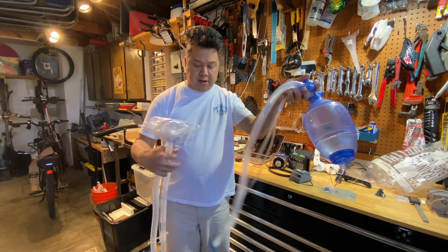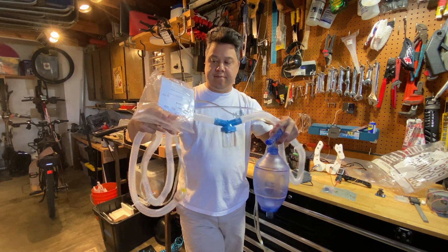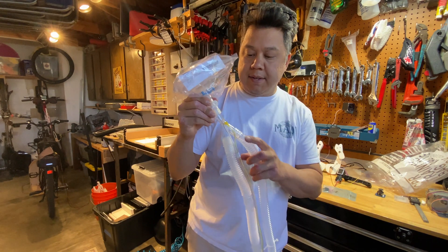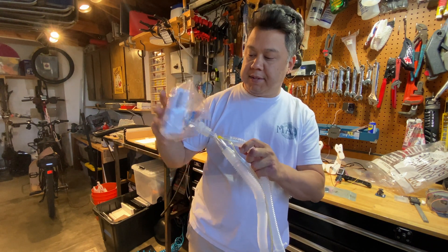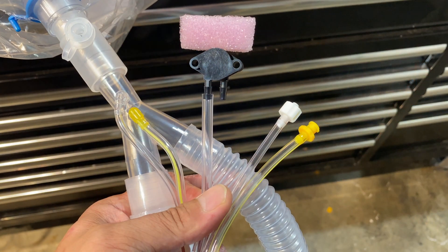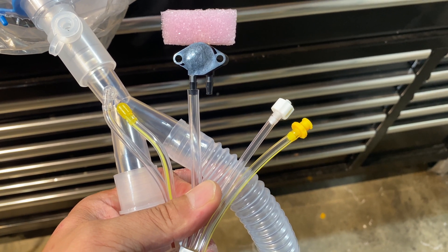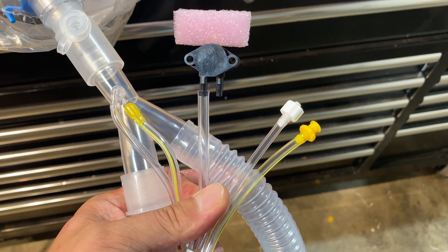Air flows through this intake hose, through a water separator cup, and into this Y which supplies air to the mask. The splitter has some tap lines and I'm using one of those tap lines to hook up my pressure transducer. This will measure pressure in the mask.